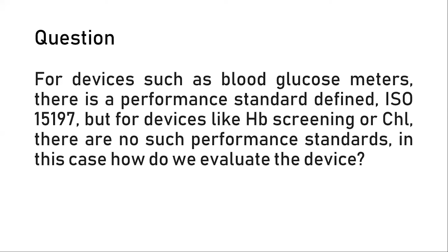Yeah, and even if you didn't actually do studies to the CLSI, taking interfering substances again as an example, maybe you didn't use that as an input when you did your original studies. Just be aware that the notified bodies may well also be considering that in best practice. You're not going to get a non-conformance to the CLSI, but you may get a non-conformance because they don't think you've sufficiently covered interfering substances, because they know that there is this internationally recognized list of interfering substances and you've missed one out. So it may not be that people are applying standards as best practice, but if there is something like that that applies in your sector, it's good to be aware of it, even if you haven't fully met it.